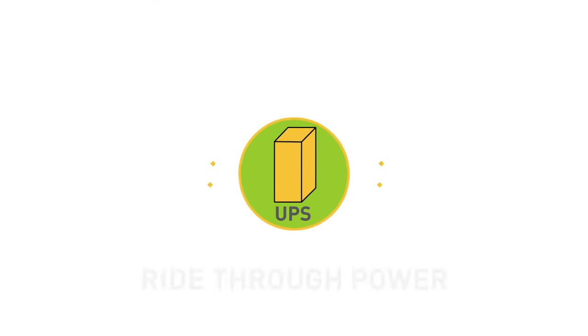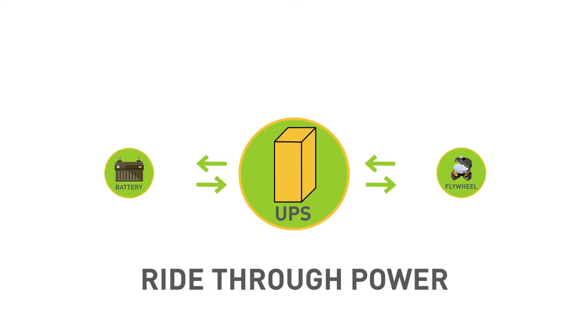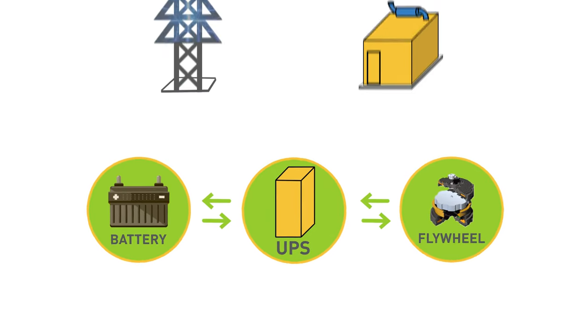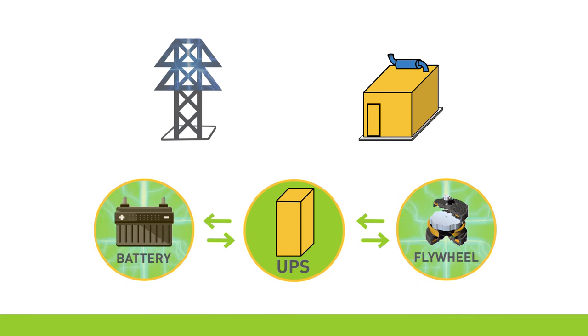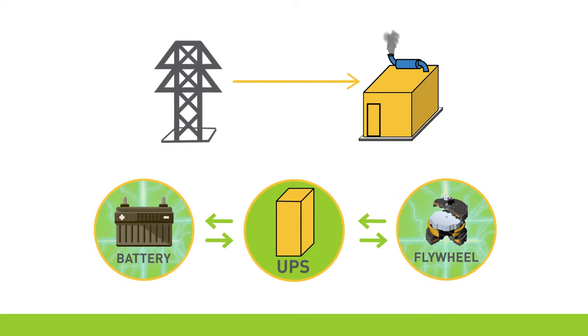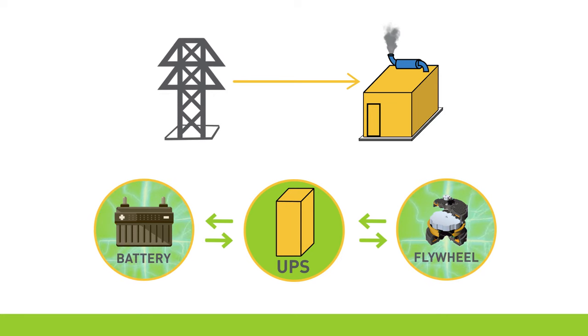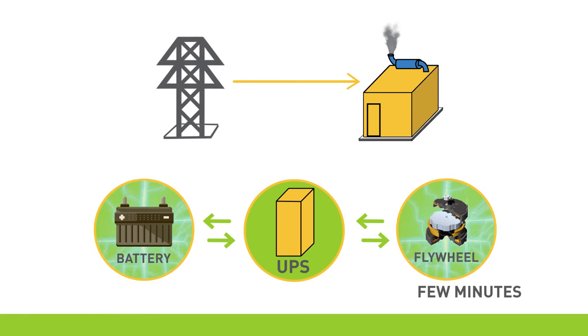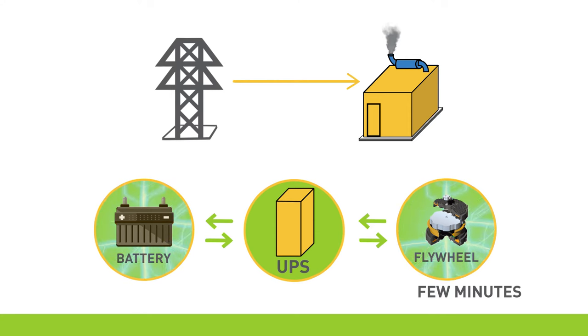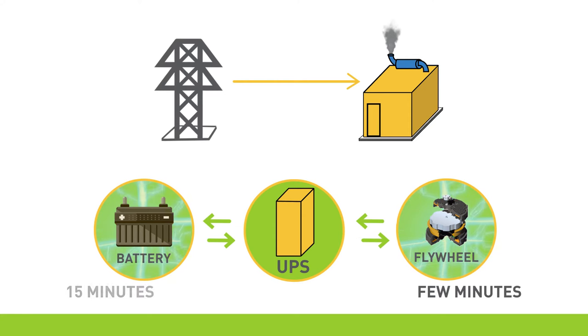The standby power provided by UPSs is known as ride-through power and can be either a battery or flywheel system. Both systems store a specified amount of energy to span the time between utility power outage and generator power startup. The flywheel UPSs, when used in series, can generally generate sufficient power for at least a few minutes. Battery systems can provide power for longer durations of 15 minutes or more. There are benefits and drawbacks with both types of systems.